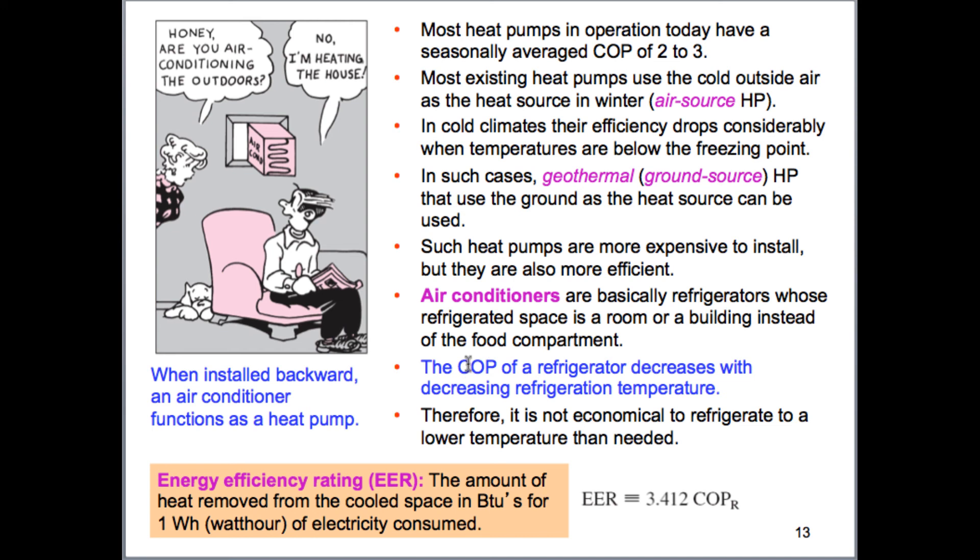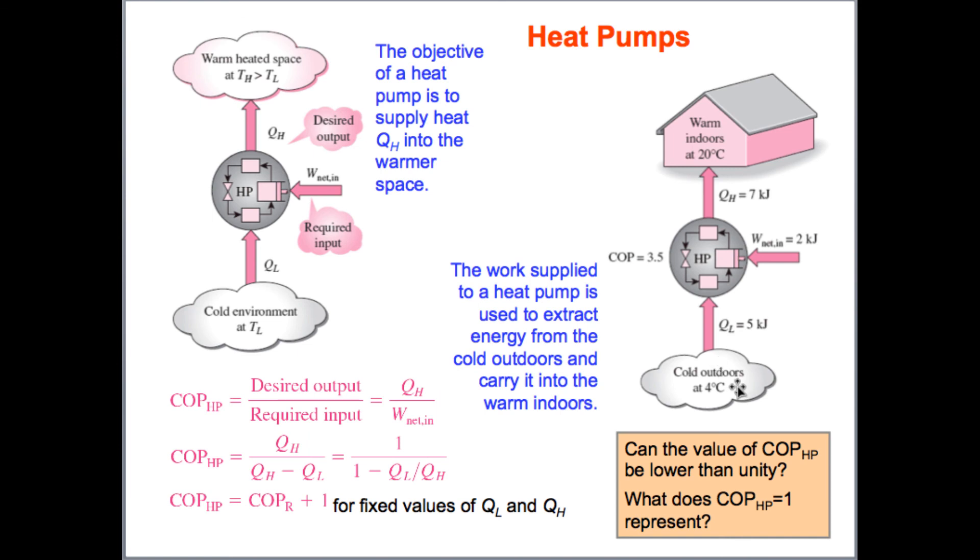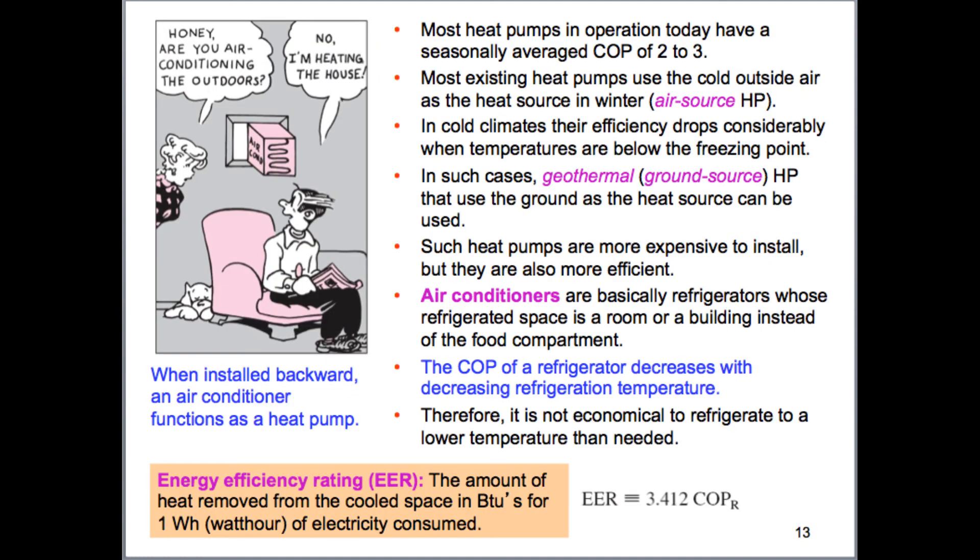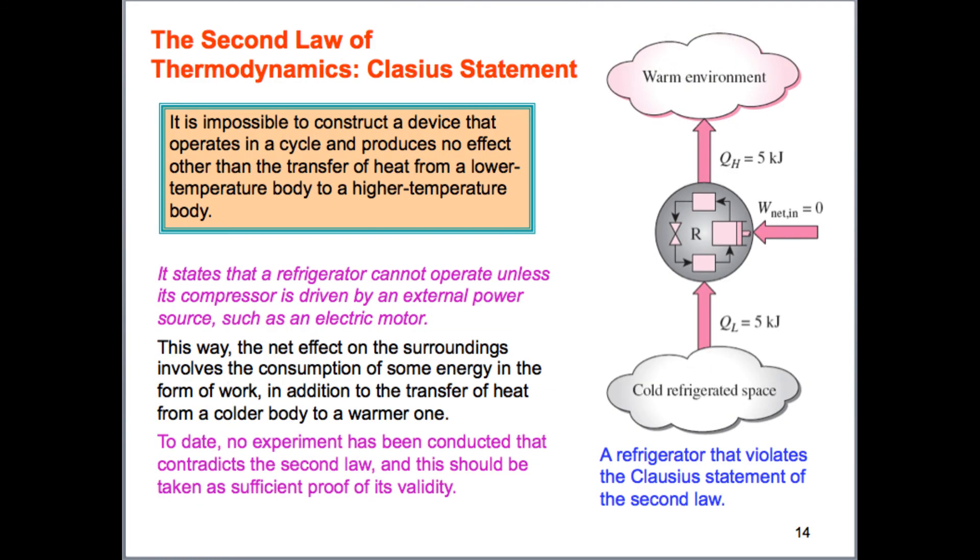So, a couple things to notice about refrigeration type cycles. One is that as the outdoor temperature, let's say here, or not necessarily outdoor, but whatever temperature is here, as this decreases, the efficiency of your refrigeration cycle is going to be decreasing. So, basically, the coefficient of performance decreases for different temperatures. So, basically, don't refrigerate something too much or too cold if you don't need to because it's going to take a lot of power to do that. Coefficient of performance that you can expect for heat pumps is between 2 and 3, and that's just basically a rule of thumb.